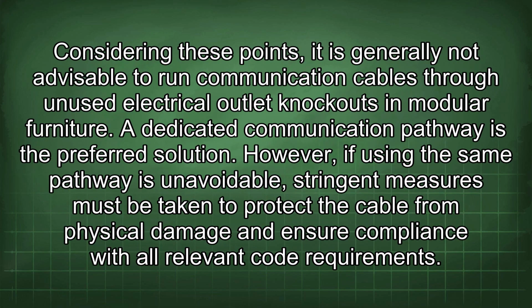Considering these points, it is generally not advisable to run communication cables through unused electrical outlet knockouts in modular furniture. A dedicated communication pathway is the preferred solution. However, if using the same pathway is unavoidable, stringent measures must be taken to protect the cable from physical damage and ensure compliance with all relevant code requirements.